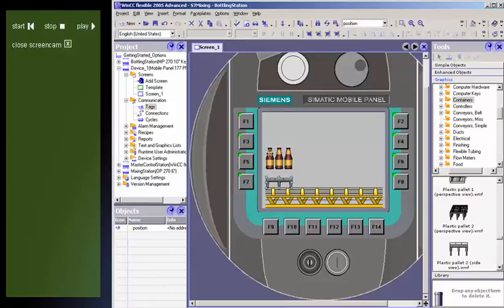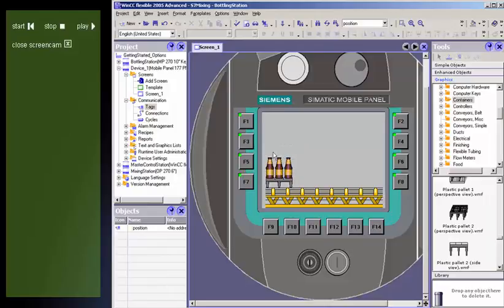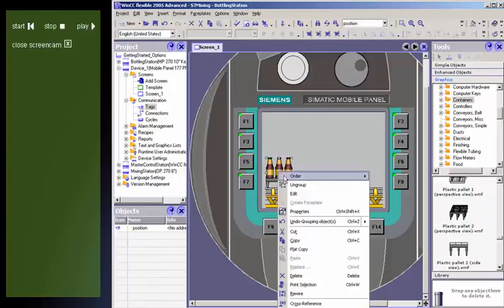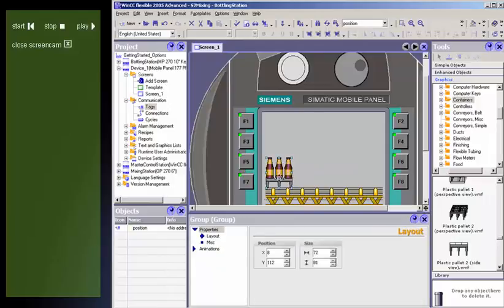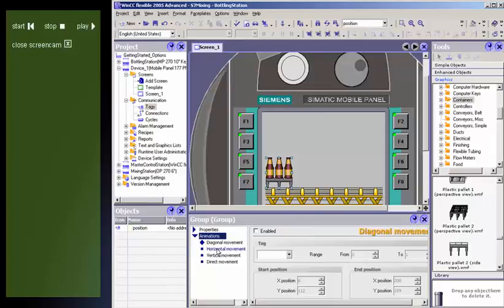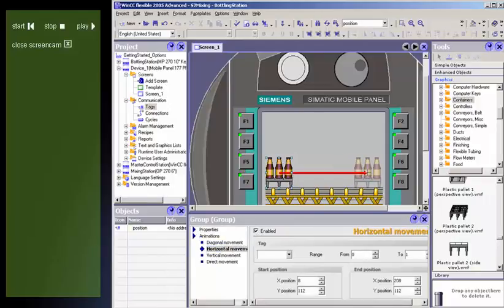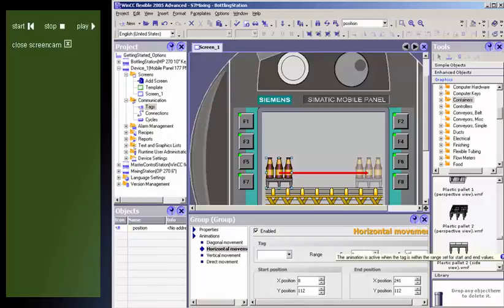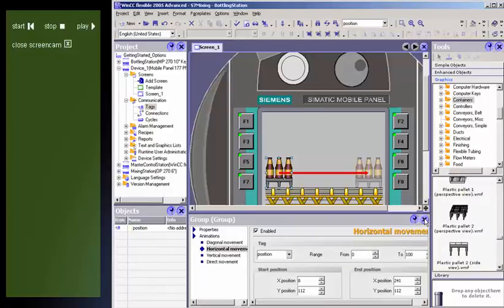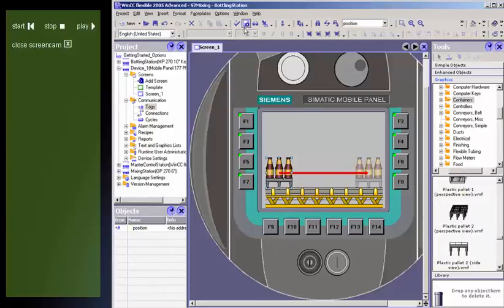You simply mark an object, for example, insert it into your process display at the desired location, and select the required type of animation. By setting a start point and an end point, you define the movement path for the object in the process display. You then assign this movement path a variable whose value represents the actual position of the object.